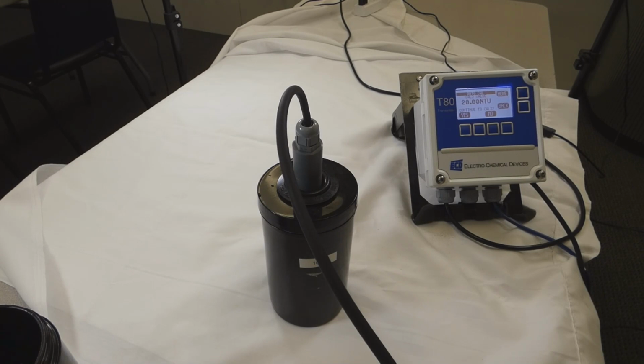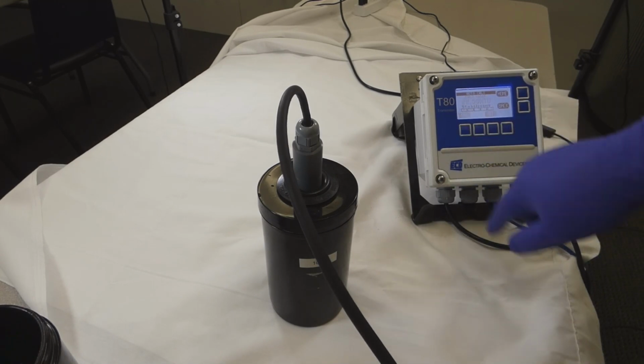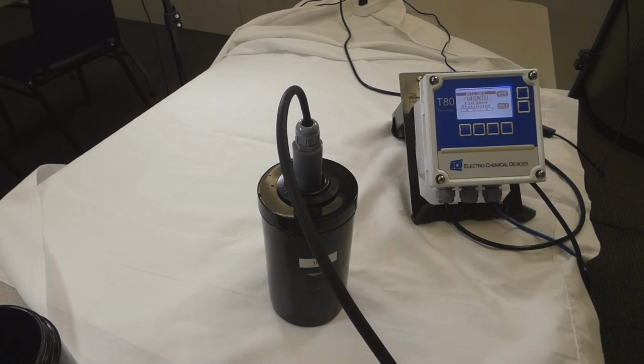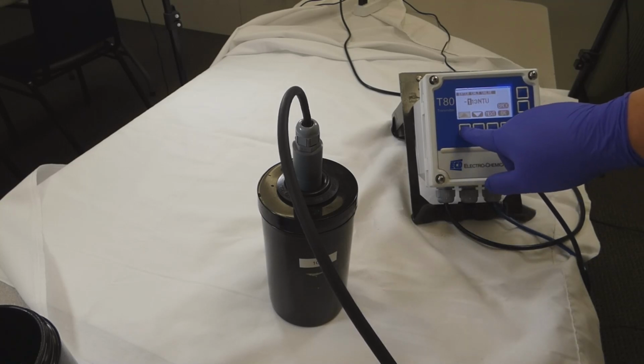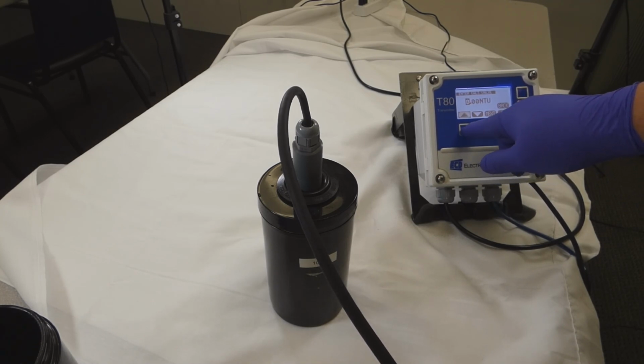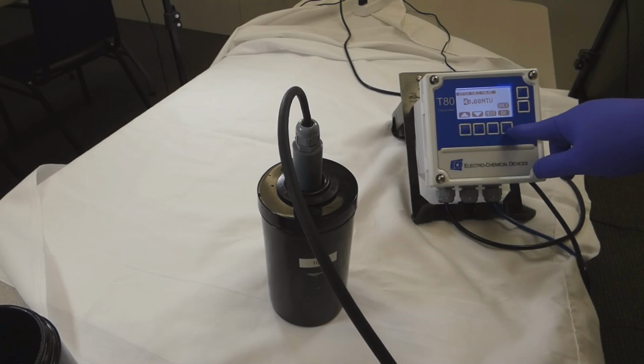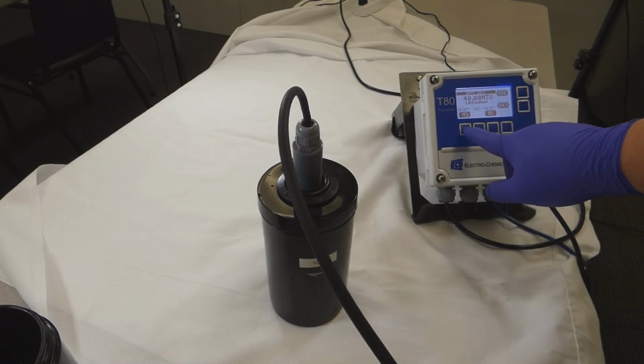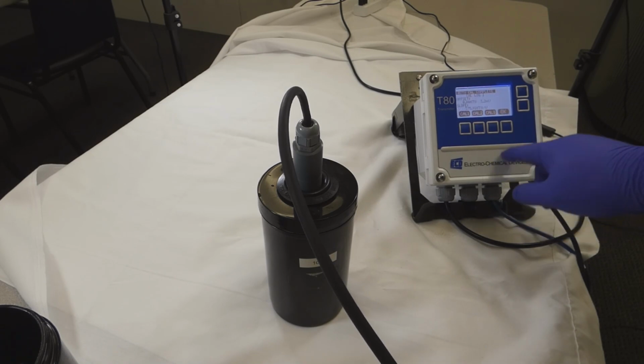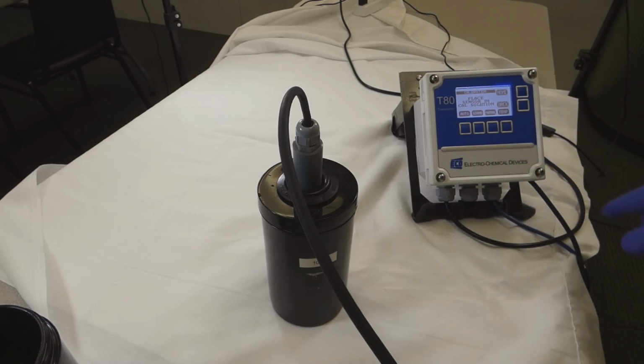Okay, after 2-3 minutes, you can now move on to Cal 3. Wait for the stabilization bar. Once stabilized, you can correct the value. In this case, this will be now 40 NTU. Press OK, accept this value, say OK, and back home. And now you're done with your calibration.